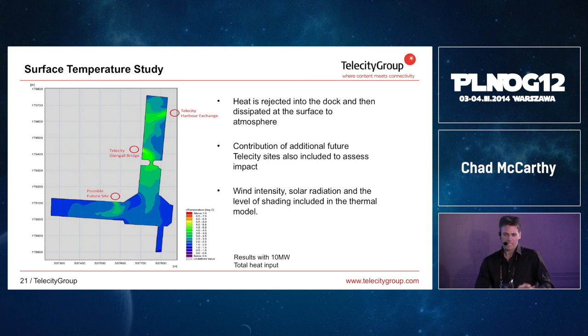And I guess what we're trying to do here is, rather than having a small area such as a dry cooler or a cooling tower, where we have a very small surface area and we compensate with a high flow rate of air to transfer heat energy, we're actually using the surface area of the dock as the heat exchanger, which you can imagine is where we save the energy, because we don't have the fan power. So we have around a 5 degree temperature increase on the surface. This is based on a 10 megawatt total heat contribution. So it's not a small amount. It's a lot of energy.